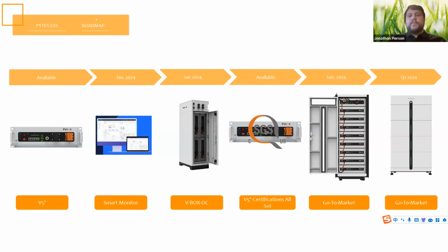Now, another battery - our latest and greatest in our low voltage family - is our stackable battery solution. These batteries you're able to stack one on top of the other and it just builds up. There's no bussing needed, it automatically busses as soon as you stack it. The only thing you'll have to wire is communications and the home runs at the very top. This comes in increments of 10 kilowatt hours up to 30 kilowatt hours, great for the residential side, easy to install, which is always one of our values at Pytes.